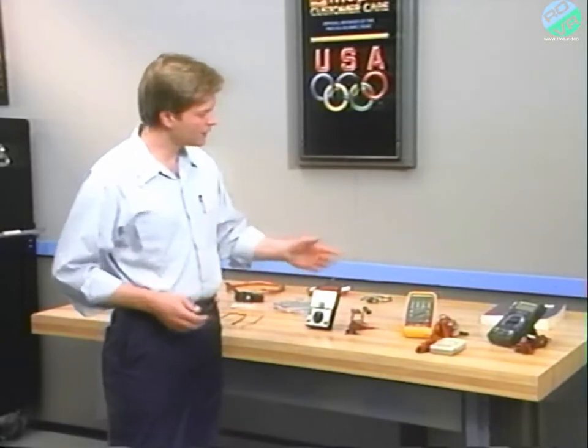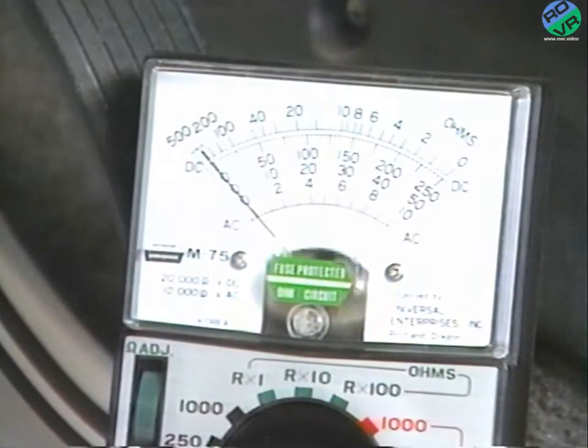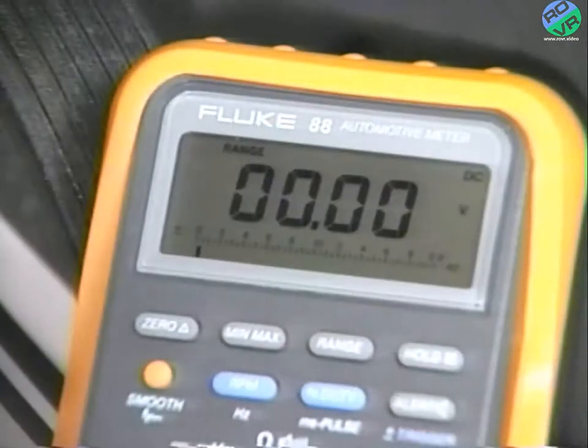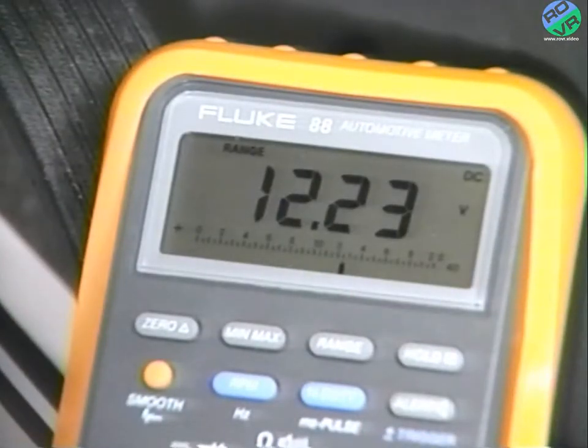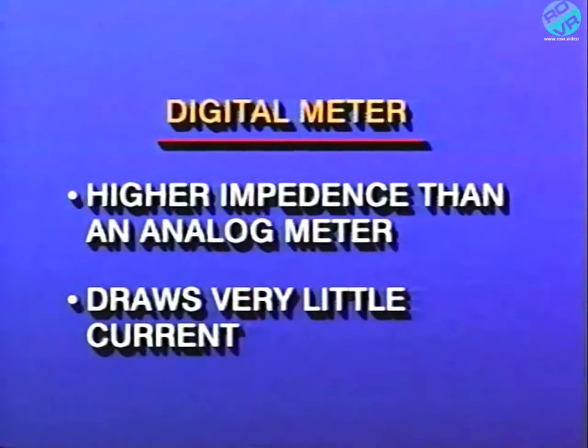There are two types of meters, analog and digital. An analog meter uses a pointer and a scale to indicate a reading. A digital meter displays the number itself. Both types of meters have their advantages and their disadvantages. In general, a digital meter will have a higher impedance than an analog meter.